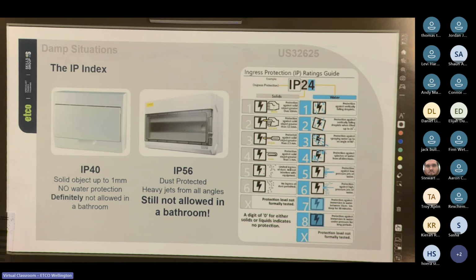A bathroom is a restricted area that is not allowed to have a switchboard in it. However, when people do up their houses, they take the switchboard that used to be in the laundry, which was legal back in the day, and they turn the laundry into a bathroom. All of a sudden, I have a switchboard in the bathroom. Obviously, they didn't have any electrician come through when they did this work, because the electrician would have taken one look and gone, maybe I should put that on the other side of the wall. So if you come across a job like that, you can just take the switchboard and move it to the other side of the wall, even if it is the outside of the building. As long as the main switch is within 2 meters of the floor, then it's okay. But yeah, never a bathroom, never a laundry. My preference, outside, in the hallway, in the garage. Probably hallway, then outside, then garage.